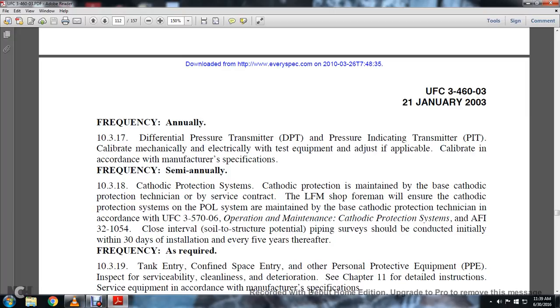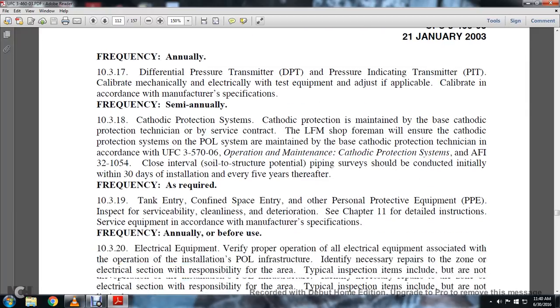Cathodic protection system. Cathodic protection is maintained by the base cathodic protection technician or service contractor. The liquid fuels maintenance shop will ensure the cathodic protection system for the POL system is maintained with the base cathodic protection technician in accordance with UFC 3-570-06, Operation and Maintenance: Cathodic Protection Systems, and AFI 32-1054. Close interval soil-to-structure potential piping surveying should be conducted initially within 30 days of installation and every 5 years thereafter.